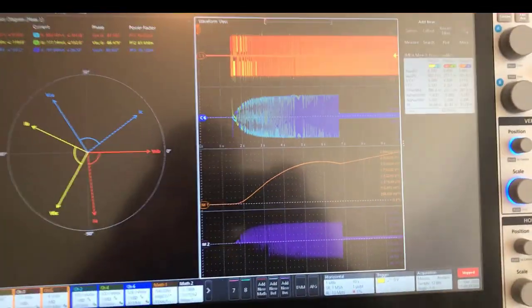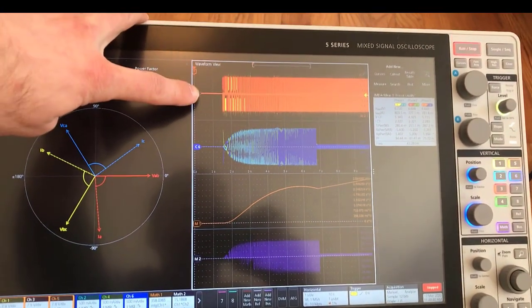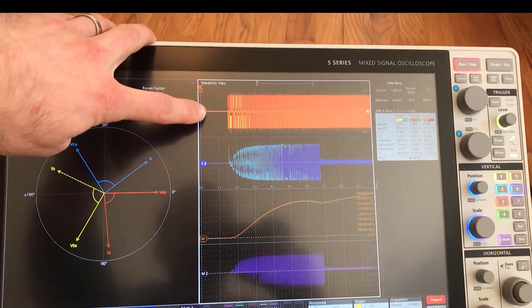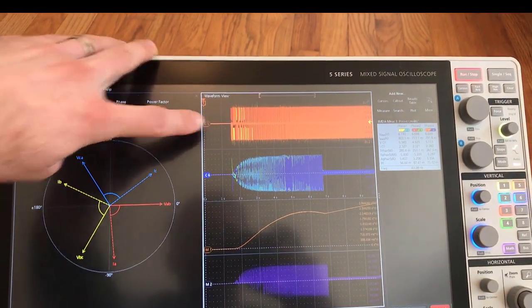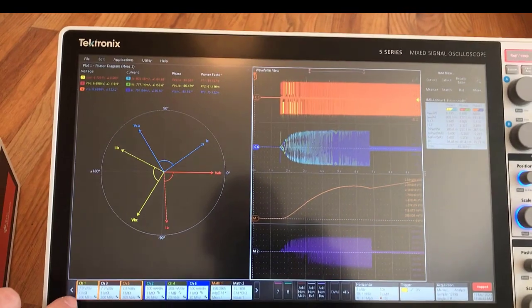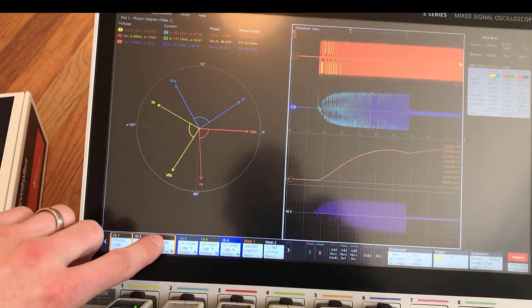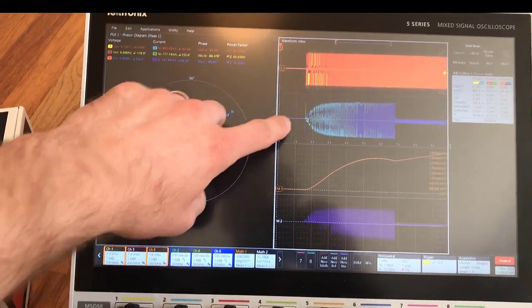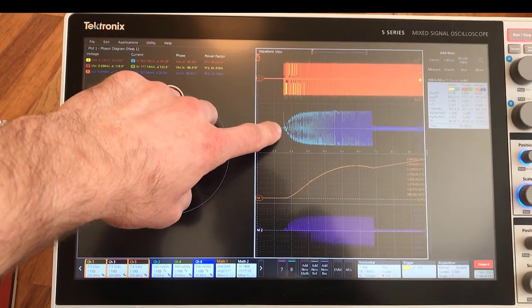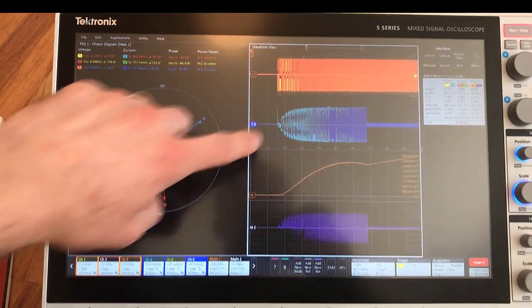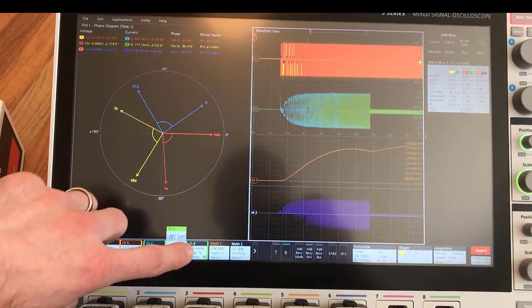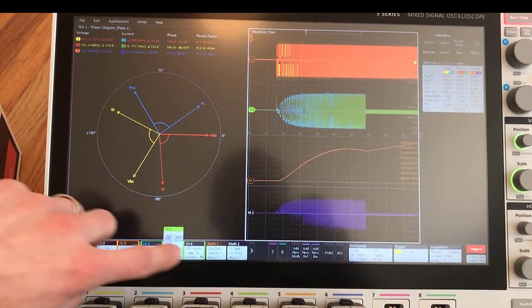Here on the scope you can see the user interface where we've got the three differential voltage lines that are overlaid over each other—that's channel one, three, and five—and then the three phase current measurements here on channels two, four, and six.